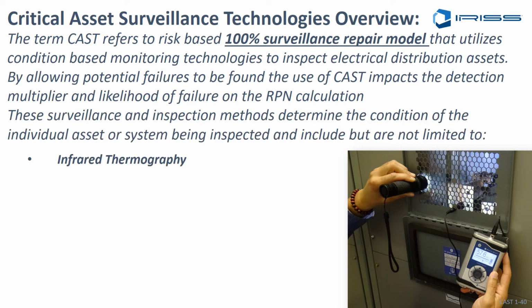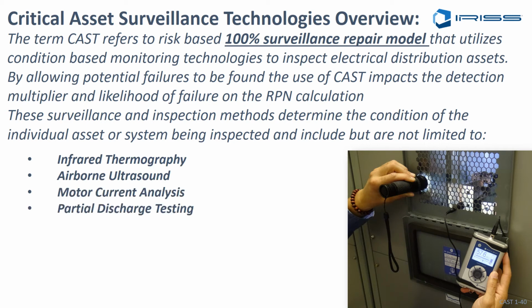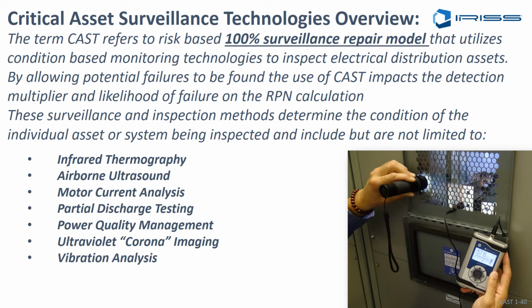The surveillance methods that we utilize in a CAST program are infrared thermography, airborne ultrasound, motor current analysis, PD testing. Power quality management is something you might do. Ultraviolet cameras, again, is something you might do. Vibration analysis, especially on rotating motors. The electrical faults will give a different vibration signature, and we can detect whether it's mechanical or electrical in motors, pumps, etc. Alignment testing, visual inspections. You can start to add oil analysis. All of these things can be brought into a CAST program depending on what you're doing. So it's not just limited to the things I'm showing you on the screen here.